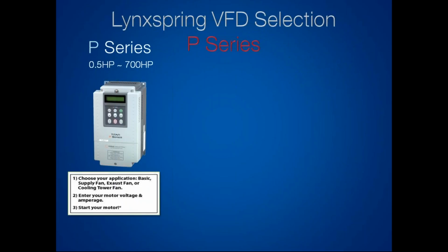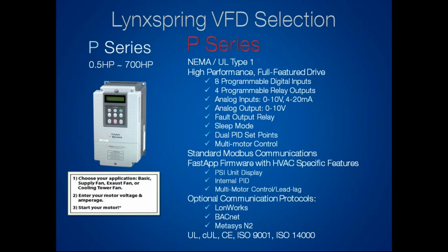So let's talk about the P-Series VFD that you guys have access to. If you just want to go ahead and click the next arrow. So the P-Series drive has a lot of the same features and functionality that any other manufacturer's drive is going to have, okay? What this drive has that's really special is what's called Fast App firmware, okay? This Fast App firmware has HVAC-specific applications built right into it. So let's say you've got a cooling tower, right? You're going in, you're going to set up your drive, you're setting it up for a cooling tower.